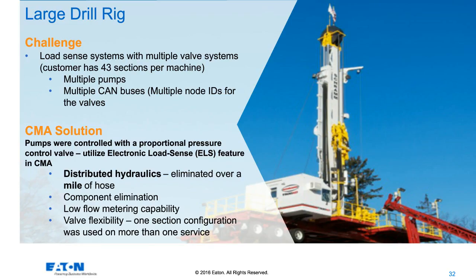This first one is a large drill rig. We work with a customer that has 43 sections per machine, so a lot of valves on there. Not a very dynamic machine, but it has multiple pumps and multiple CAN buses. By utilizing our electronic load sense feature in CMA, we were able to give them distributed hydraulics, eliminating over a mile of hose. With the pressure sensors within the valve, we eliminated a number of ancillary pressure reducing valves that they had on the system, since that's now encompassed in the CMA valve.